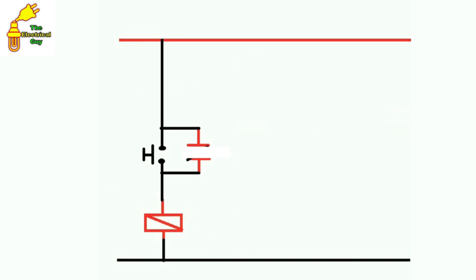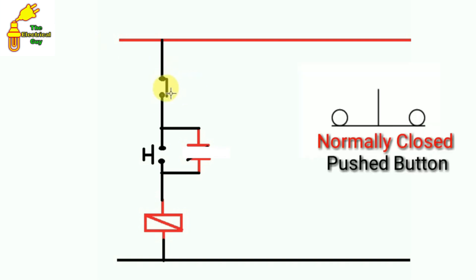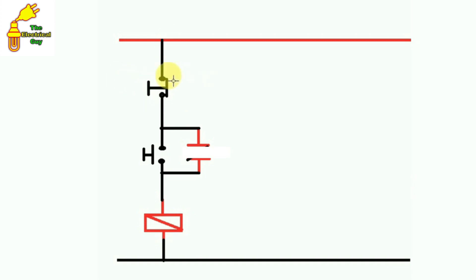For this we have to connect a push button — which type we must use so that the contactor can be turned off. We break this circuit and at this place connect a stop push button. For the stop push button we use a normally closed push button. The symbol of a normally closed push button is of this type — this is our stop push button. In normal condition it is NC; when we press it, it opens and restricts the current to flow forward.